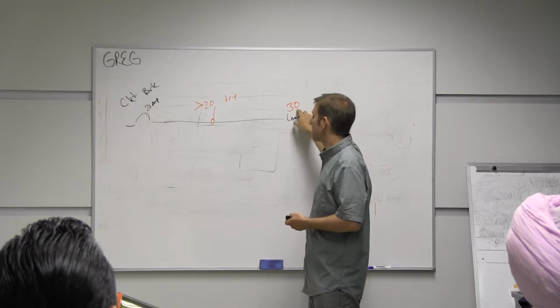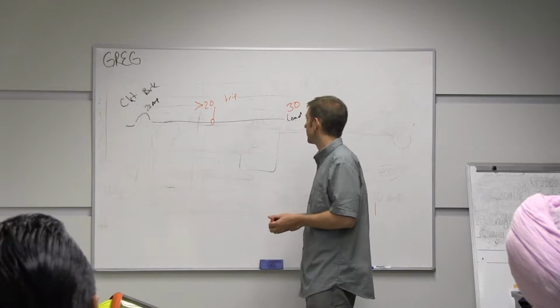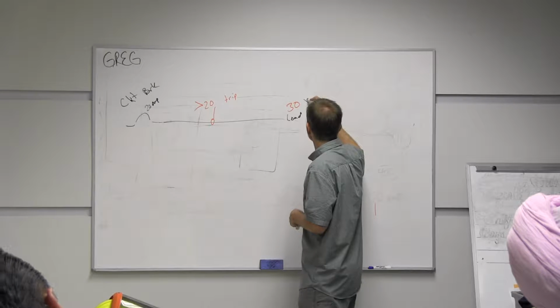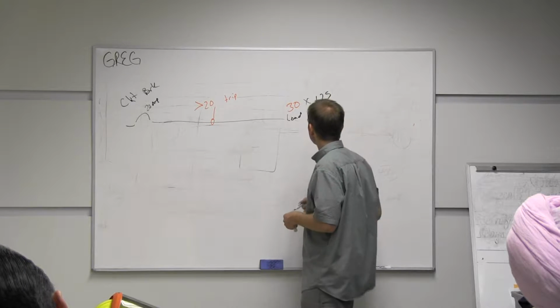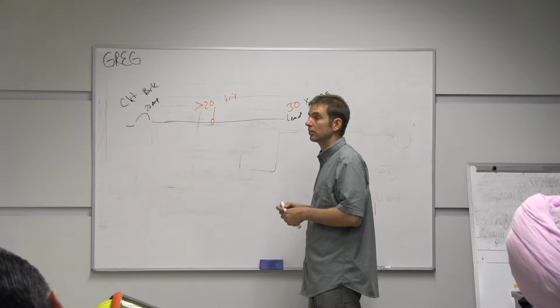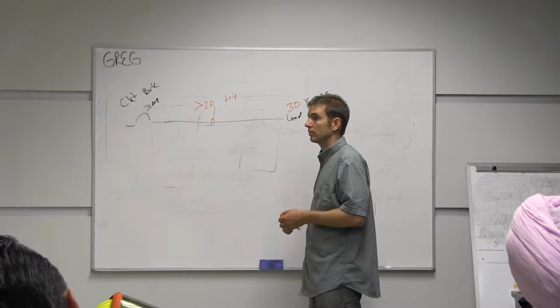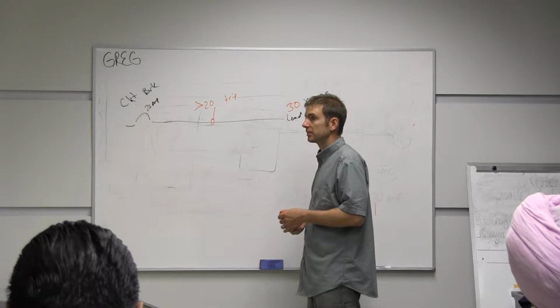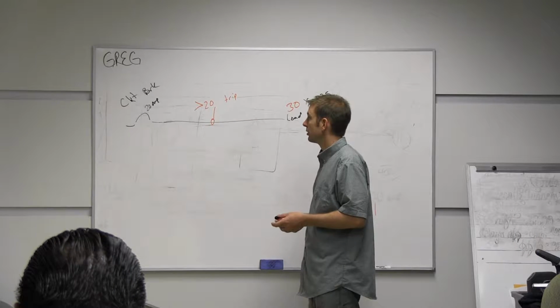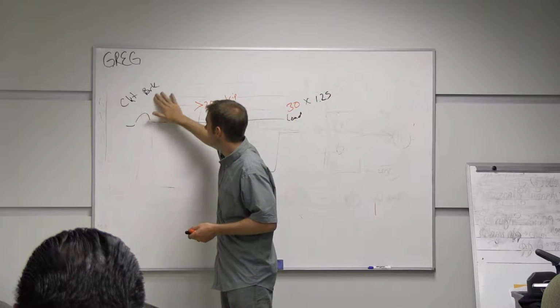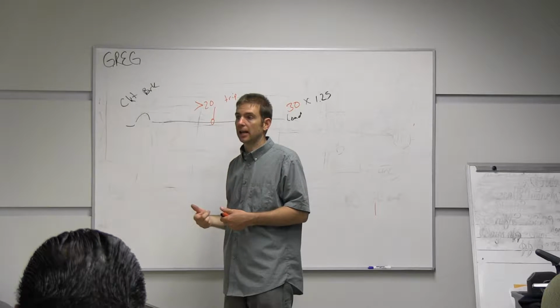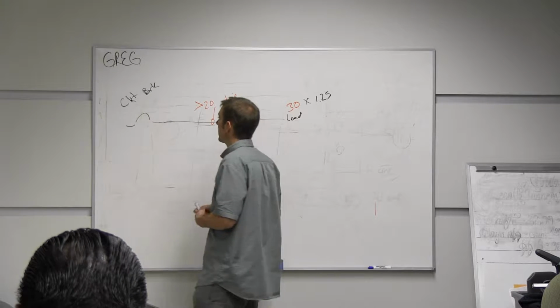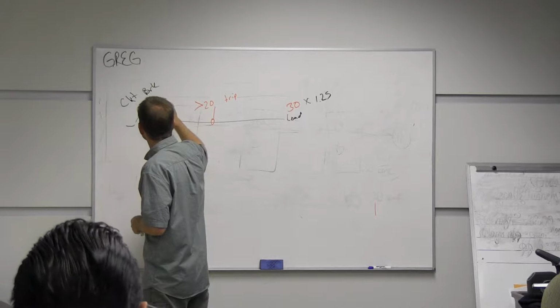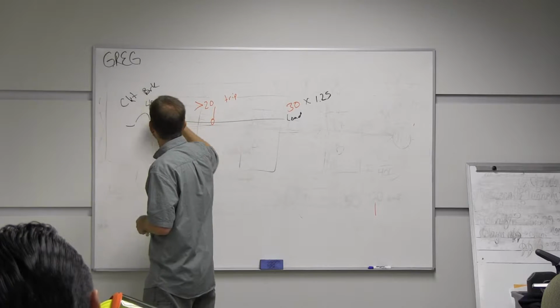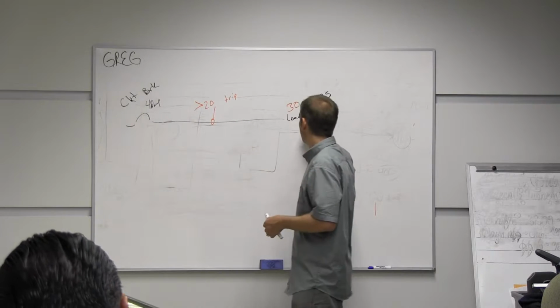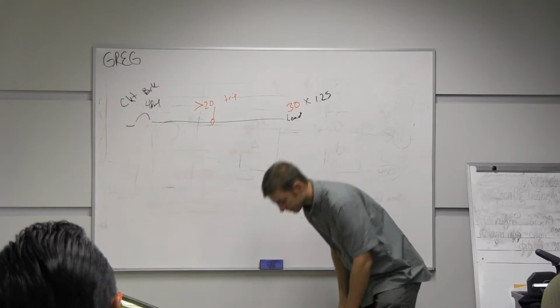So we're going to multiply the 30 amps by 125%. So 125% of 30 is 37.5. So do we have a 37.5 amp breaker? No, so we go to the next standard size. The next standard size would be a 40 amp breaker. So a 40 amp breaker is what we put on 30 amps of lighting load.